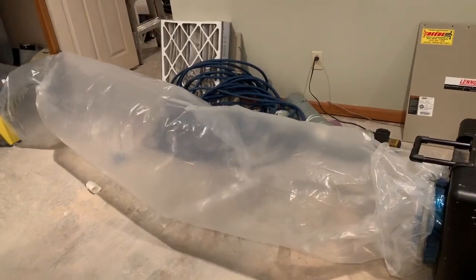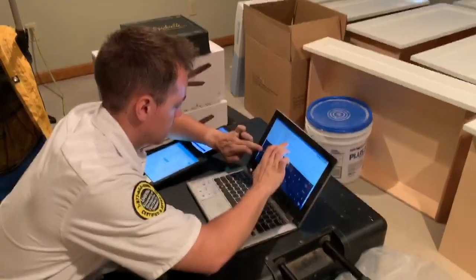Can I cut the airflow down in comfortable areas and still remain comfortable? Anytime we curtail the air in those areas, we're going to force that air to go someplace else. Duct leakage is huge — in our area, we typically find 30 to 40% duct leakage. So here we are manipulating the air using registers, and 30 to 40% of that air is going someplace we don't even know. Sealing your ductwork, either manually or professionally, can reduce that leakage to next to nothing so we know exactly where our air is going.